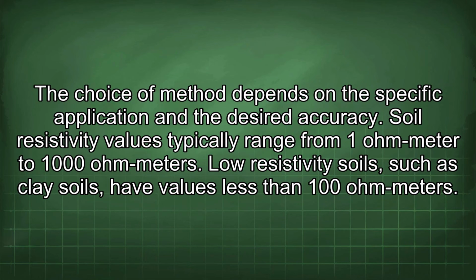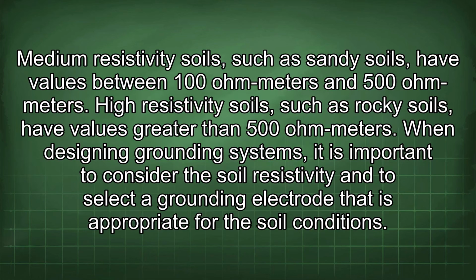Soil resistivity values typically range from 1 ohm meter to 1000 ohm meters. Low resistivity soils, such as clay soils, have values less than 100 ohm meters. Medium resistivity soils, such as sandy soils, have values between 100 ohm meters and 500 ohm meters. High resistivity soils, such as rocky soils, have values greater than 500 ohm meters. When designing grounding systems, it is important to consider the soil resistivity and to select a grounding electrode that is appropriate for the soil conditions.